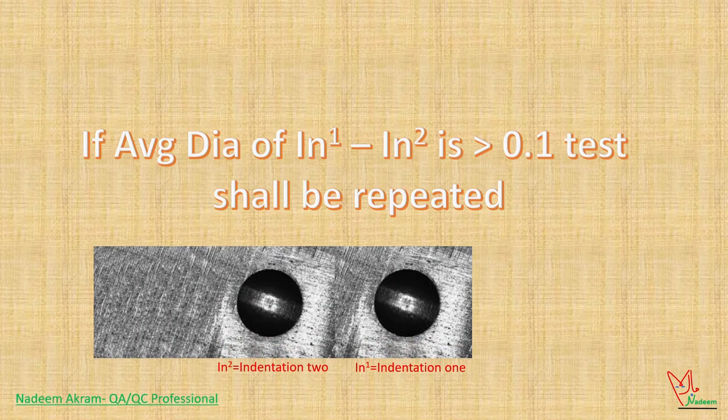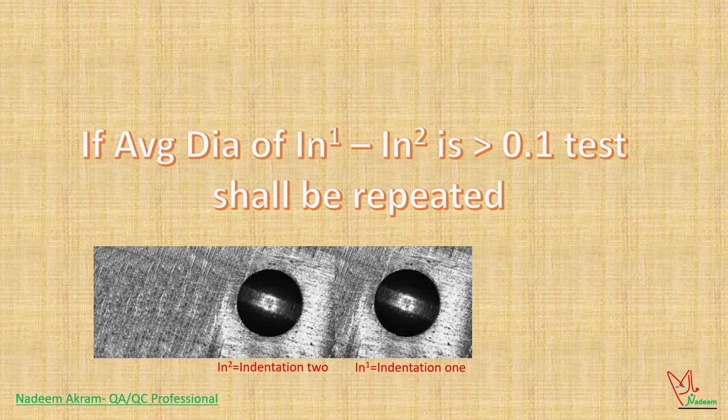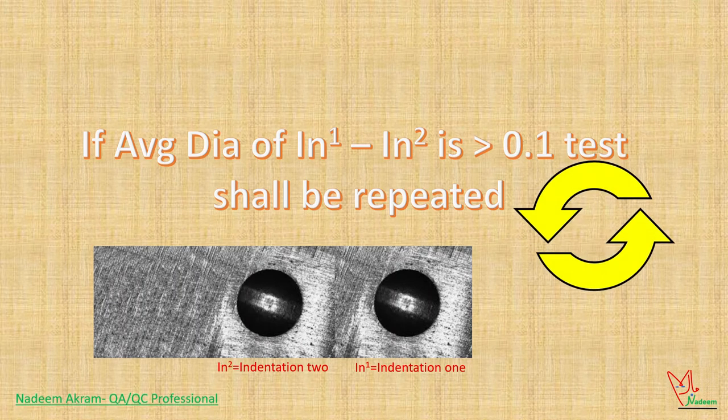If the diameters of two indentations made on test surface differ more than 0.1 millimeters, then the readings shall be discarded and the test shall be repeated.